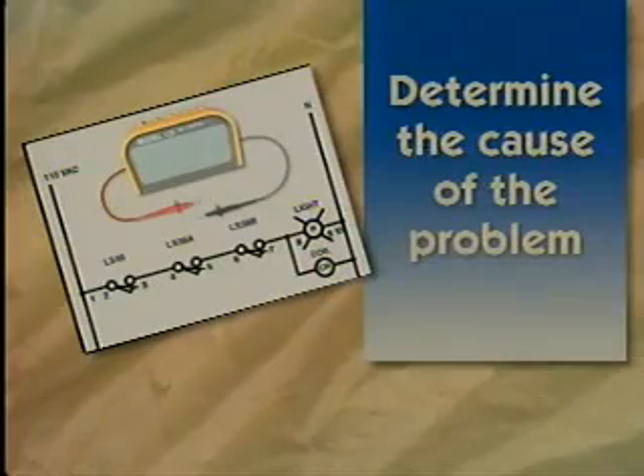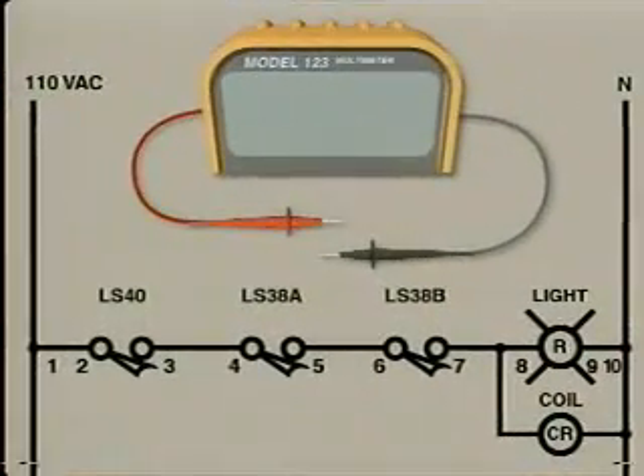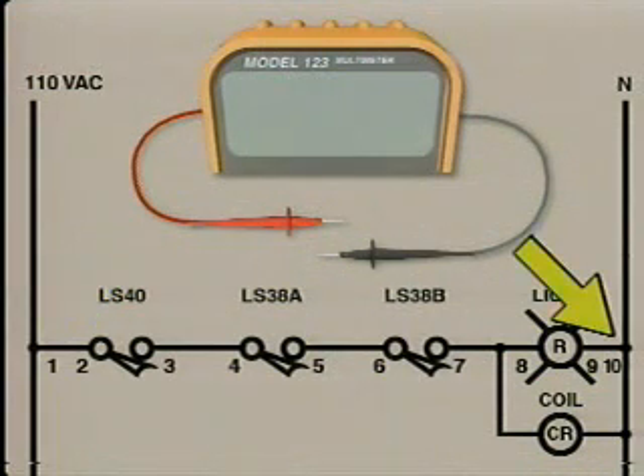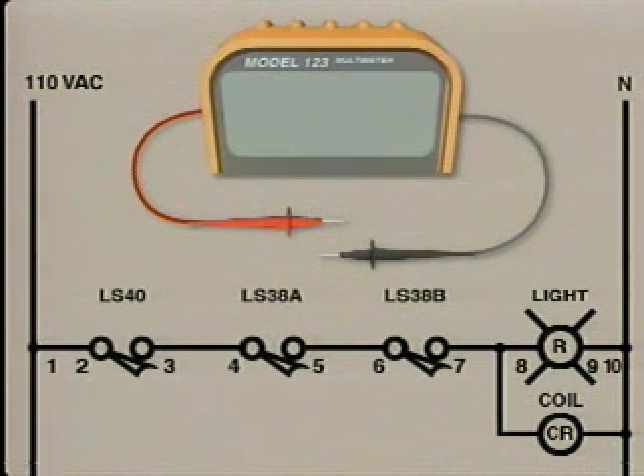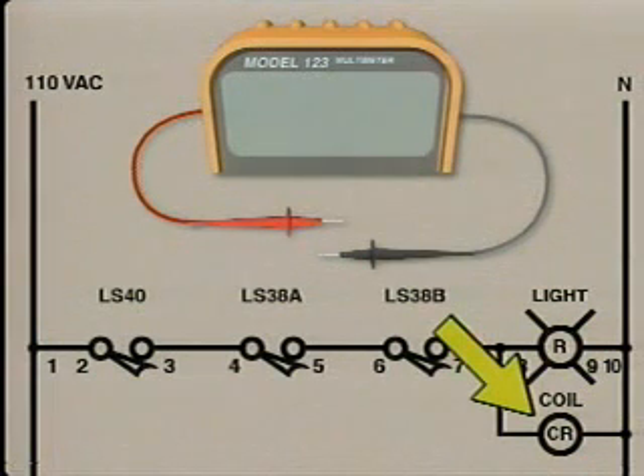Faced with this new problem, the electrician should go back to the third step of the basic troubleshooting procedure and determine the cause of this problem. Returning to the control circuit illustration, the electrician decides that the best thing to do is make sure that the rest of this circuit is working properly before moving on to any other part of the system. He knows that there is a completely closed path from test point 1 to test point 10 because the indicator light is on. He also knows that his previous work did not conclusively prove that the relay's coil was operating properly. All he did was eliminate the coil as a possible cause of the first problem.